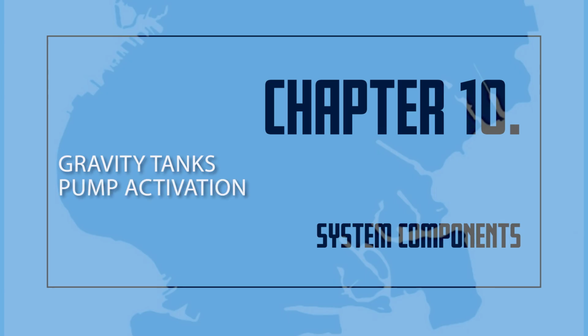Pump activation. A fire pump can be started automatically or manually. The pump can be started automatically by an electric controller or an engine controller. These controllers activate the pump when there is a drop of water pressure or water flow in the fire protection system. The controllers are adjusted so that a minor drop in water pressure or minor increase in water flow due to a small leak will not activate the pumps. The controllers for the fire pumps are expensive, require extensive maintenance and periodic testing. Where an electric motor drive is used, a standby power generator is sometimes required. If an engine controller is used, the appropriate fuel storage tanks should be filled and checked regularly.